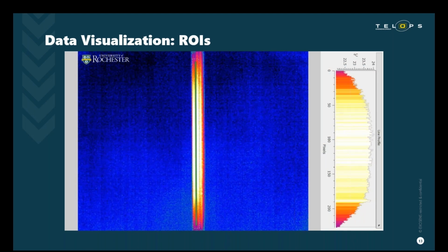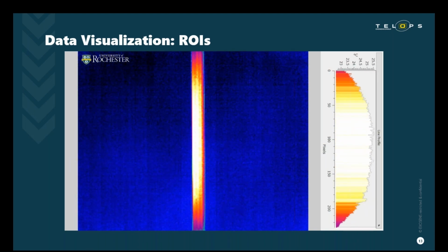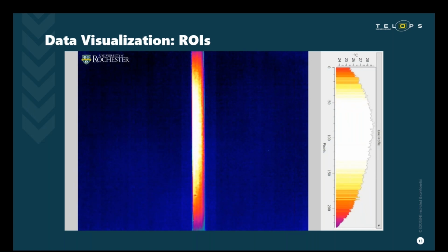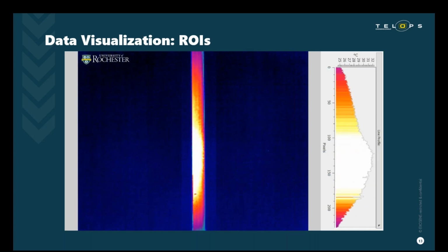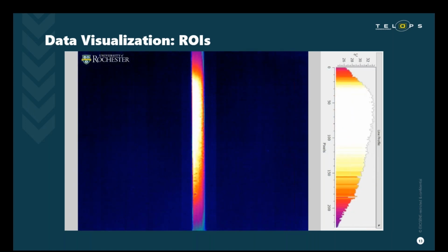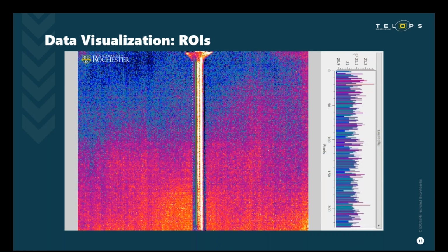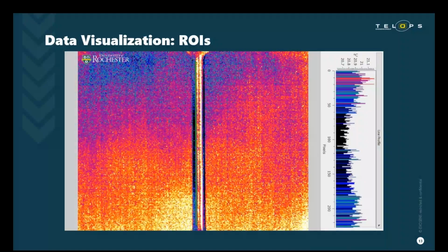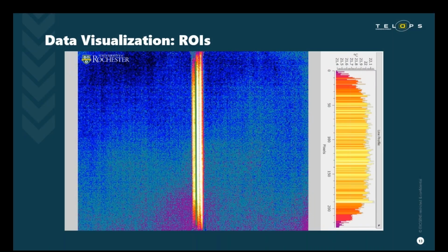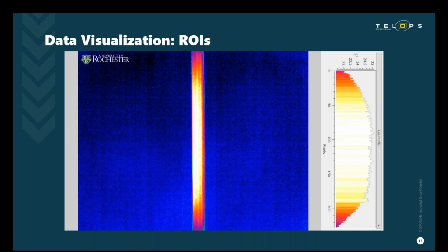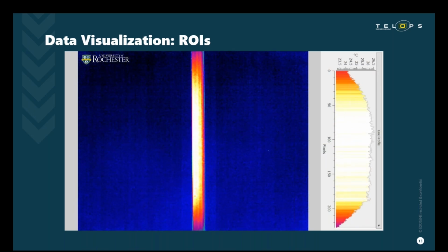So this is an aluminum sample undergoing a tensile strength test that we imaged in coordination with researchers from the University of Rochester. And you'll see here this wave of temperature that rises up the gauge before the sample eventually fractures at the top. That is uncharacteristic for these samples. However, with our full field thermal viewing and our line profile, we are able to see this irregularity in clear detail.